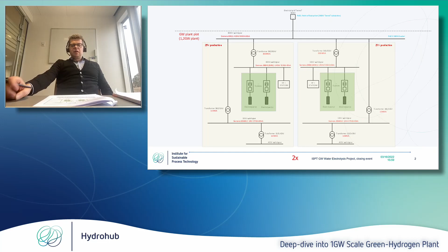Then the power converters. The power converter transforms, or converts, the low voltage from the secondary winding side of the transformer into DC that you're able to feed into the electrolyzer. Most of these converters are fitted with what we call thyristors or IGBTs, which are two types of power electronics with different properties.